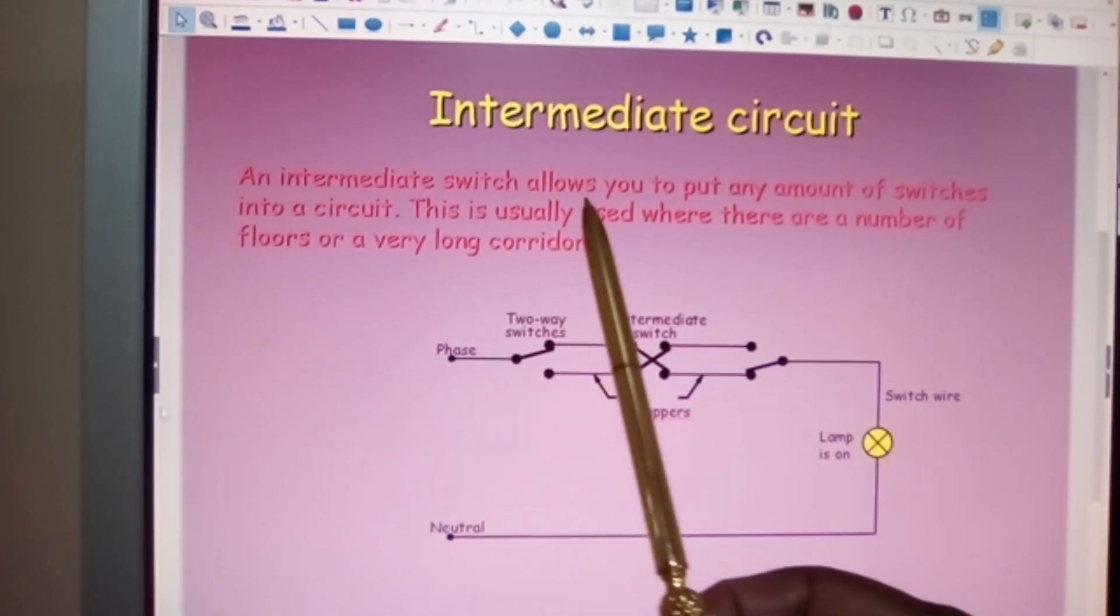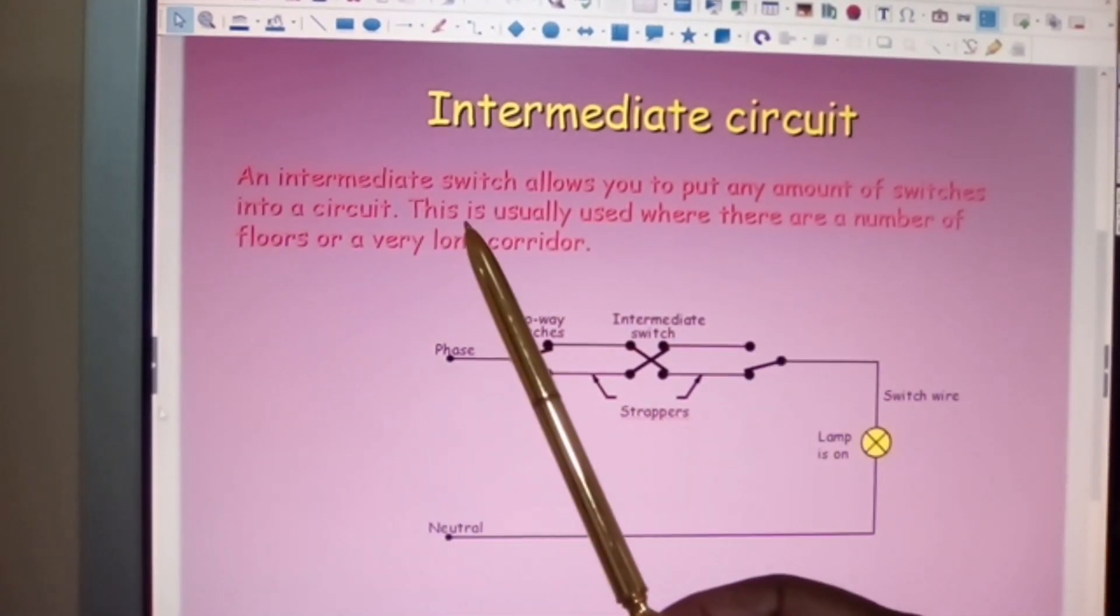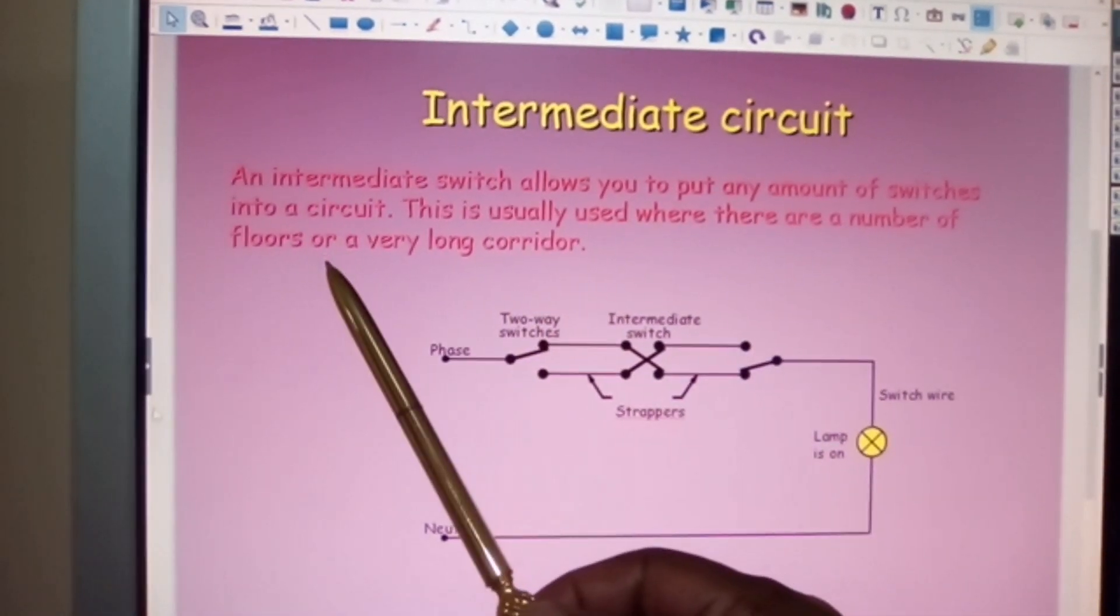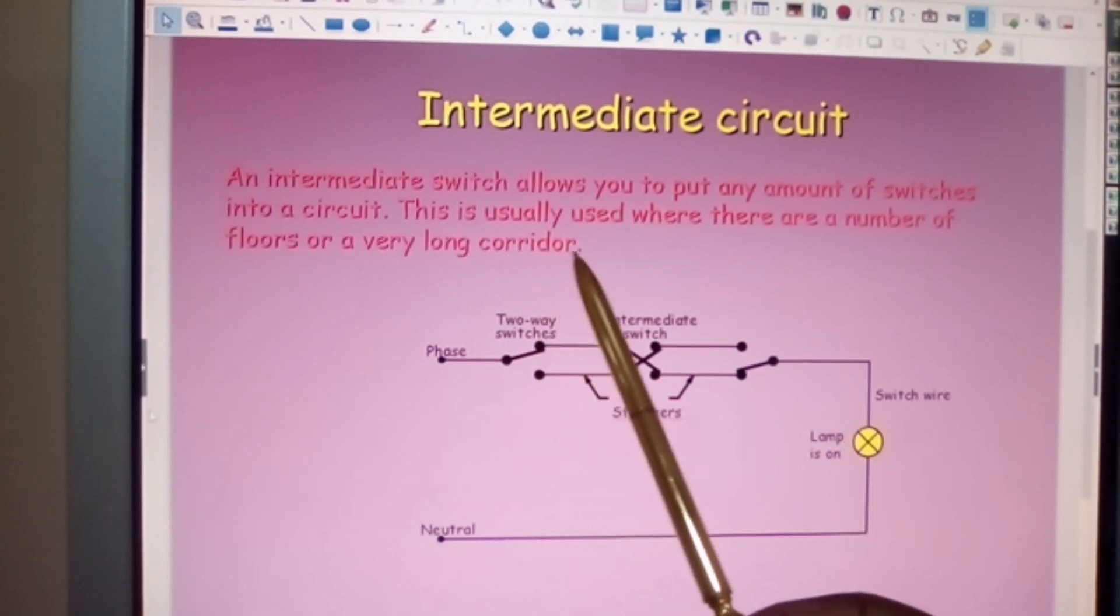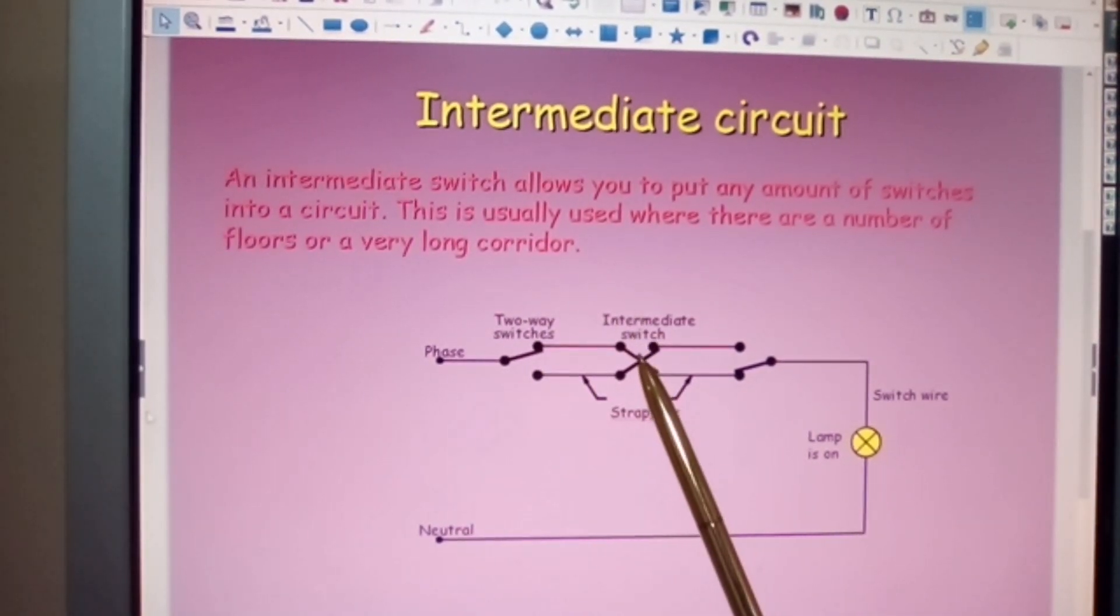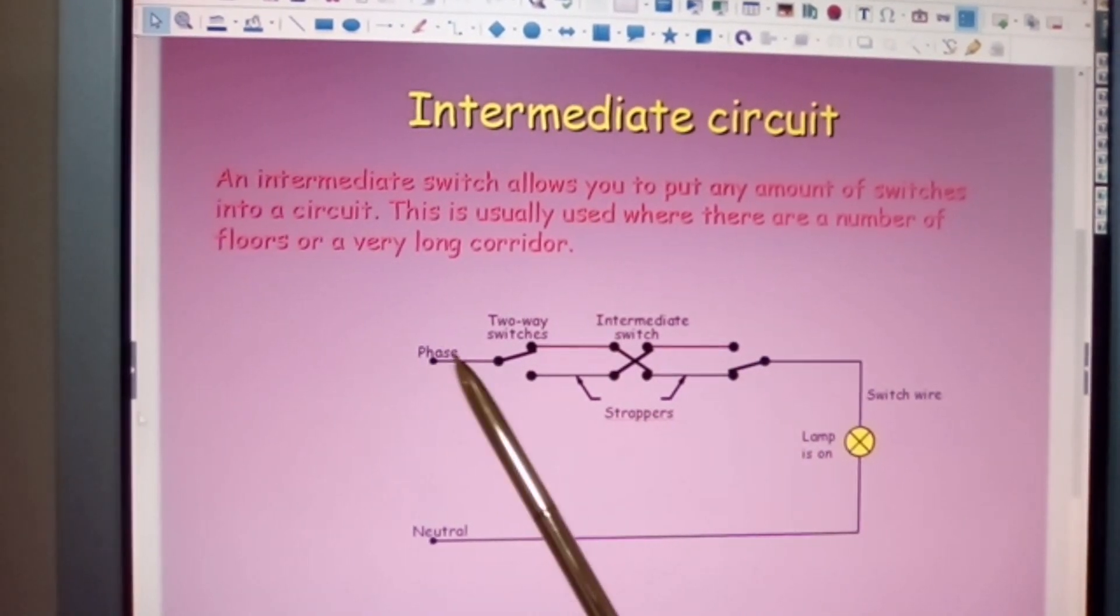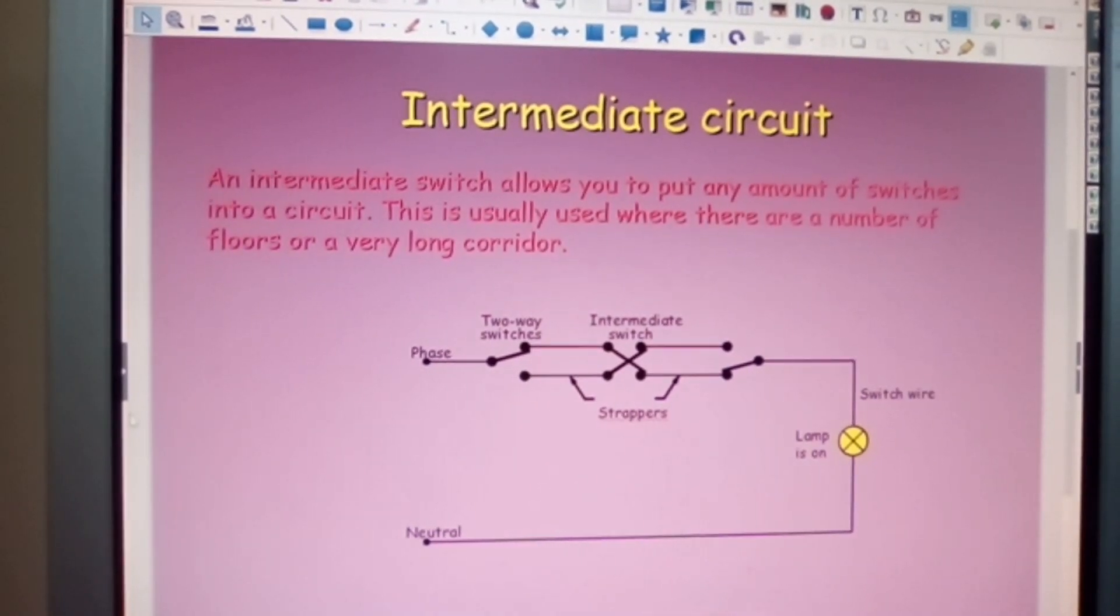The intermediate switch, or intermediate circuit if you prefer. An intermediate switch allows you to put any amount of switches into a circuit. This is usually used where there are a number of floors or a very long corridor. So this could be at the beginning of your corridor. This could be in the middle of your corridor. This could be at the end of the corridor. And again, you'll notice that the phase conductor comes to the switch. It has not come through the neutral.